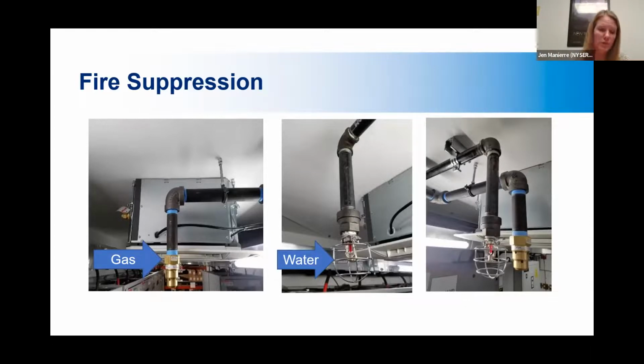So a non-water based fire suppression system might work in that case. You could see the non-water based system go off first if something goes wrong, to snuff out the flames. If the flames happen to have been coming from batteries and you need to cool them down, you might have the water system be designed to be triggered next if needed. So you could have one or the other or both, depending on how it's designed.